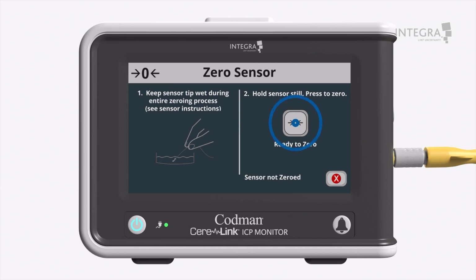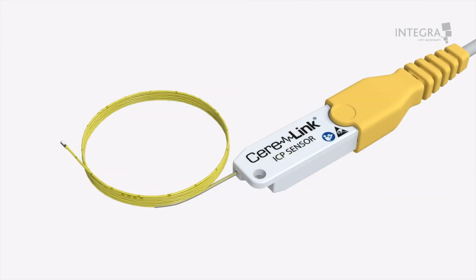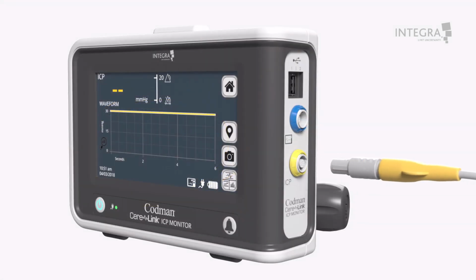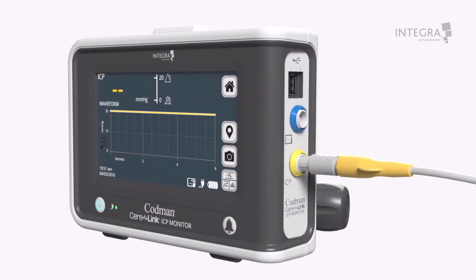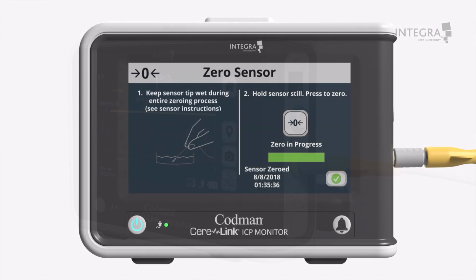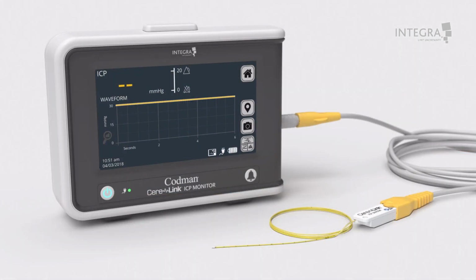Press the Ready to Zero tab. You will note a 0 in progress on the screen. When sensor zeroing has been successful, the date and time will be displayed on the screen. During this zeroing process, the ICP monitor automatically stores the 0 reference value in a memory element embedded in the ICP sensor. This feature allows the user to reconnect the ICP sensor to the same or a different ICP monitor without having to readjust the 0 reference value. Press the Accept button on the lower right portion of the screen to return to the main screen. Now the ICP sensor is ready for implantation.